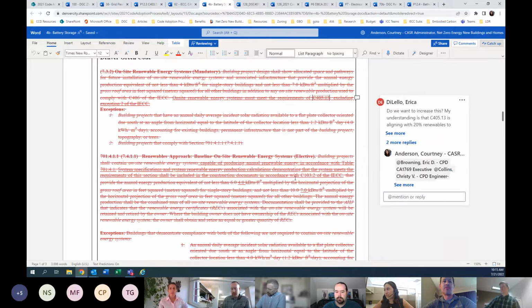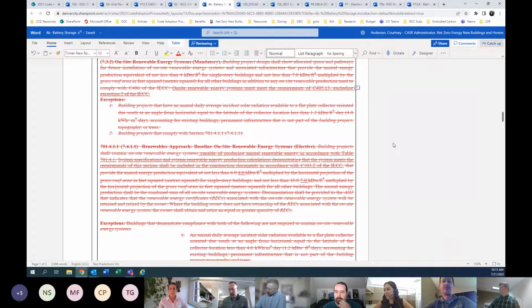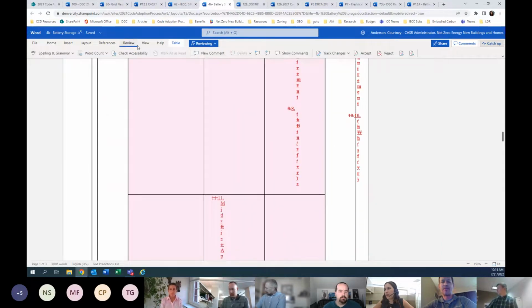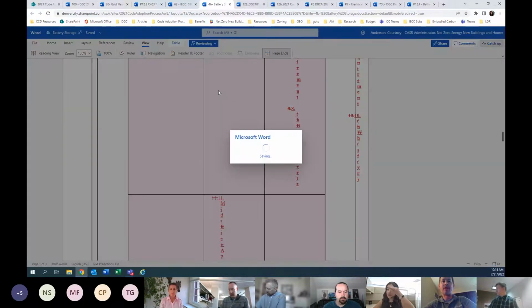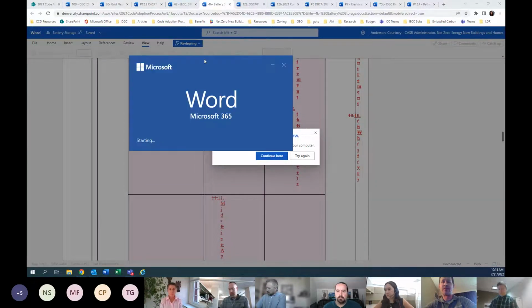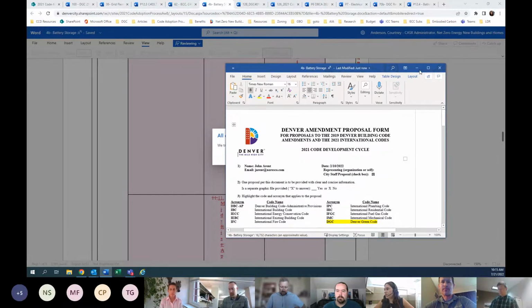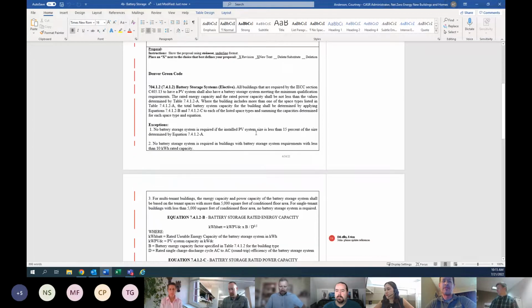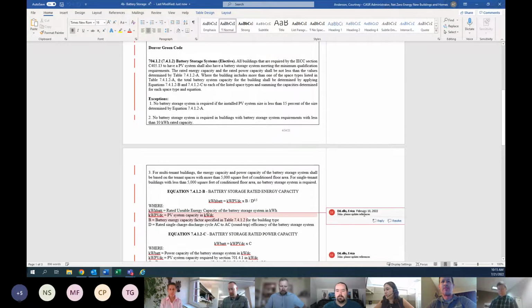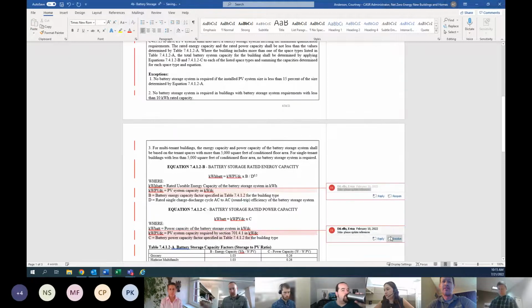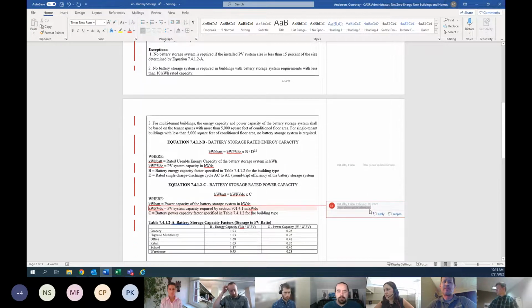So this next proposal is a green code proposal, and it follows some work that was done for the California jurisdiction that would be applicable in Denver for projects that already have planned to or are required to have photovoltaics on site or rooftop PV generation. And what the requirement is, this is slightly aspirational, but this is a requirement for projects that do have PV, that they're also required to have some level of battery storage system on site.